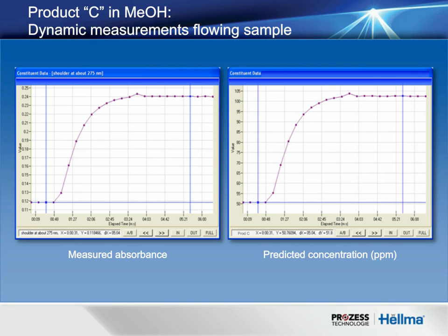Okay. What is the spectral sampling rate for the detectors? Typically 1 millisecond or 1 kilohertz measurement times is kind of the fastest. That's not just the sampling rate of the detectors, but how quickly we can process and output the data. It's typically around 1 millisecond or longer. Very few installations are actually being measured that quickly. They'll typically average over some period of a second or multiple seconds.